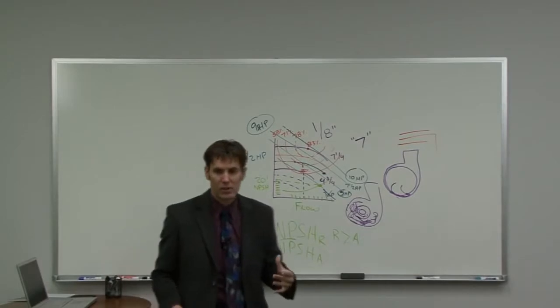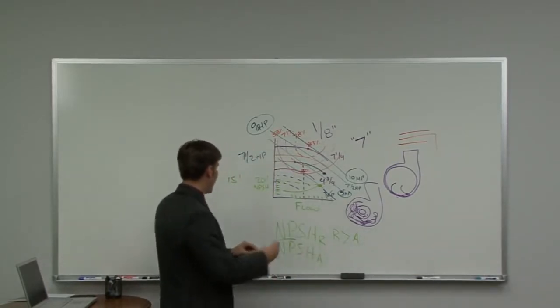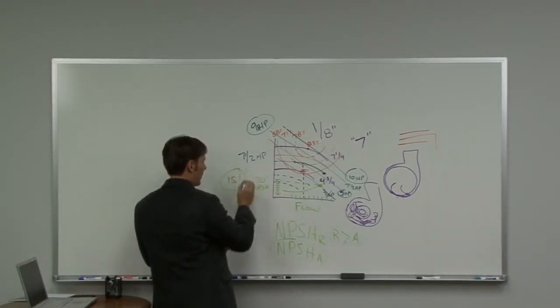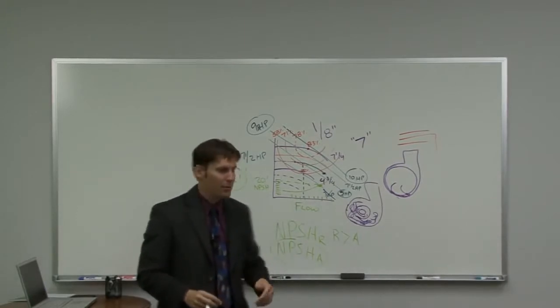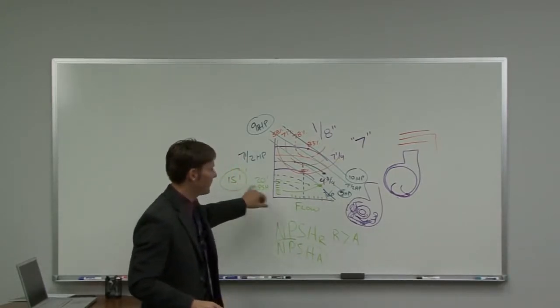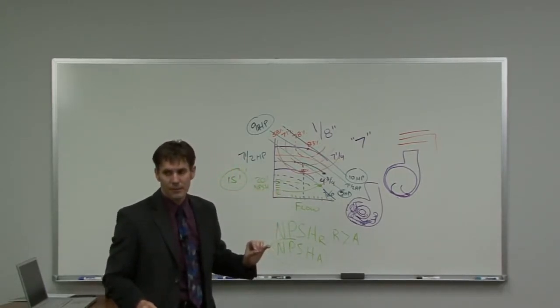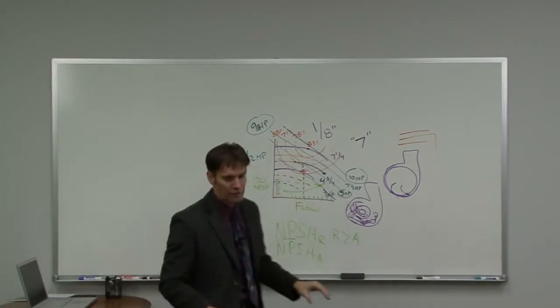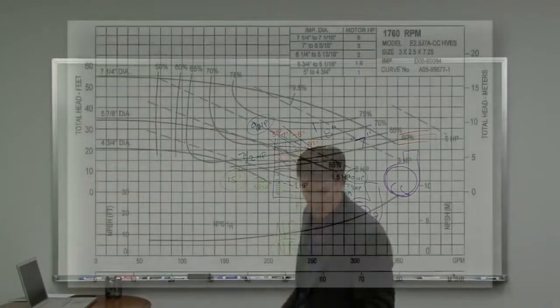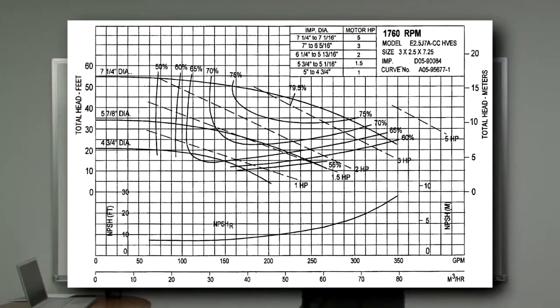When you use pump selection software, you can put in, I've calculated 15 feet available, give me a pump that does not have any more than 15 feet required. When we select pumps off of pump curves, going back to their pump curve, you want to make sure that as you determine the flow rate through that pump, your NPSH-R is going to be less than your net positive suction head available. So still looking at this curve, let's plot a point.